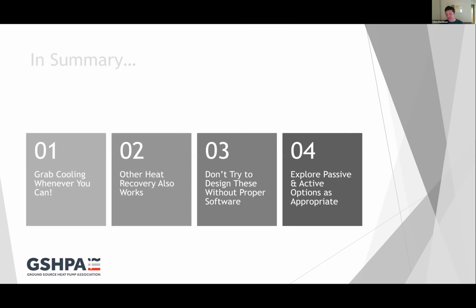So just in summary, before I take some questions, grab cooling whenever you can. Most of the systems I've designed over the years have been heating and cooling systems. The economics tend to be much better when you've got a cooling load involved in the system, as we've illustrated above. Any other heat recovery also works. So, for example, we were just talking earlier on, Laura and I, you could put some solar thermal onto a ground loop just to reject some heat into that ground loop and get the similar benefits.